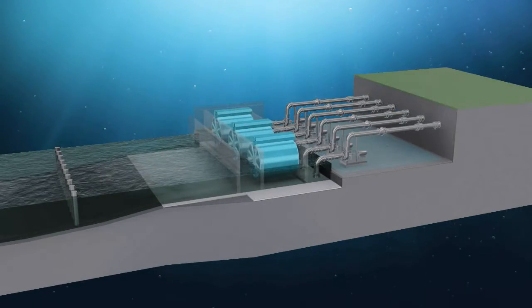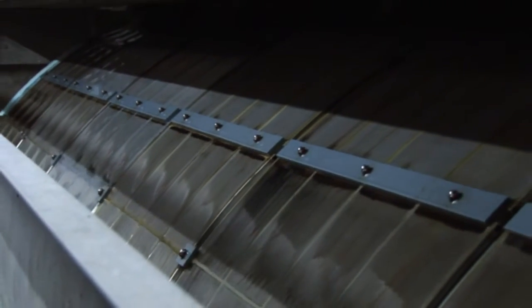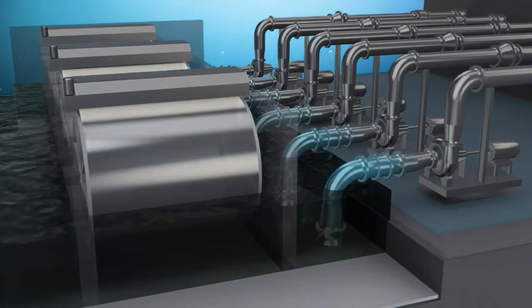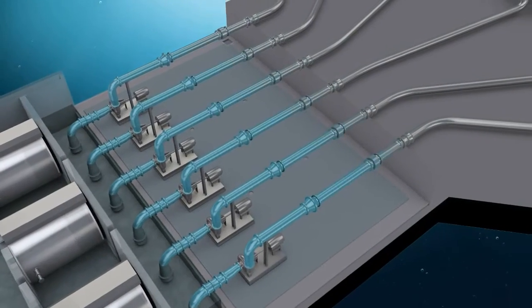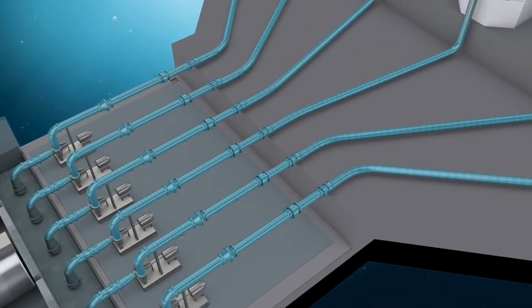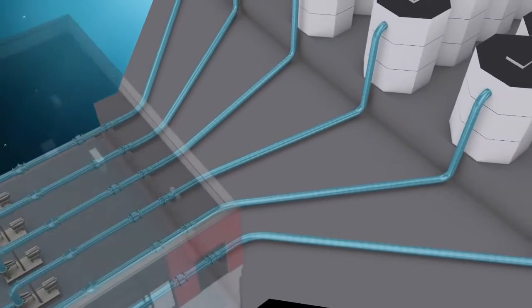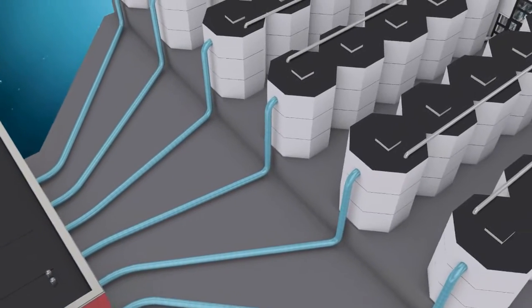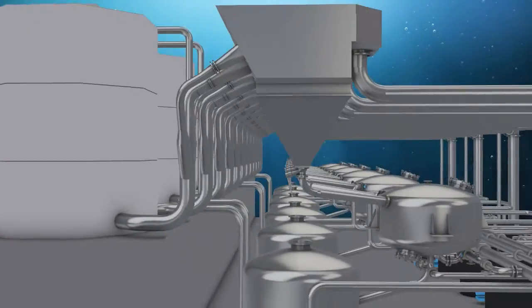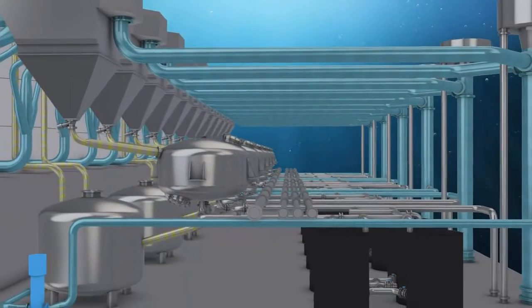The pores of the drum screens, only 0.1 millimeter, filter out any material that may clog up the system downstream, like twigs, leaves and plastic. The raw water now enters the heart of the purification process. The 6 reactors, our own suspended ion exchange design. Coagulation does not remove natural organic matter to a sufficient degree. At PWN Technologies, we built a suspended ion exchange system that will.